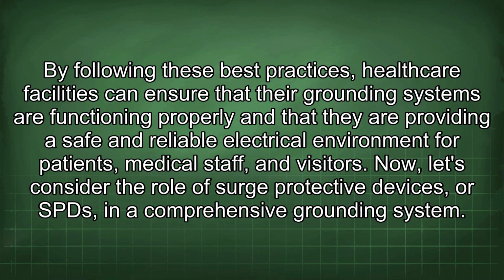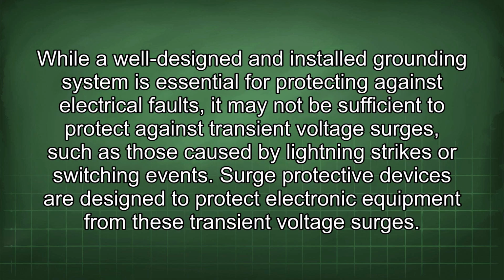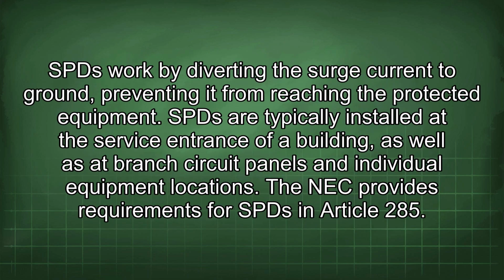Now, let's consider the role of surge protective devices, or SPDs, in a comprehensive grounding system. While a well-designed and installed grounding system is essential for protecting against electrical faults, it may not be sufficient to protect against transient voltage surges, such as those caused by lightning strikes or switching events. Surge protective devices are designed to protect electronic equipment from these transient voltage surges. SPDs work by diverting the surge current to ground, preventing it from reaching the protected equipment.